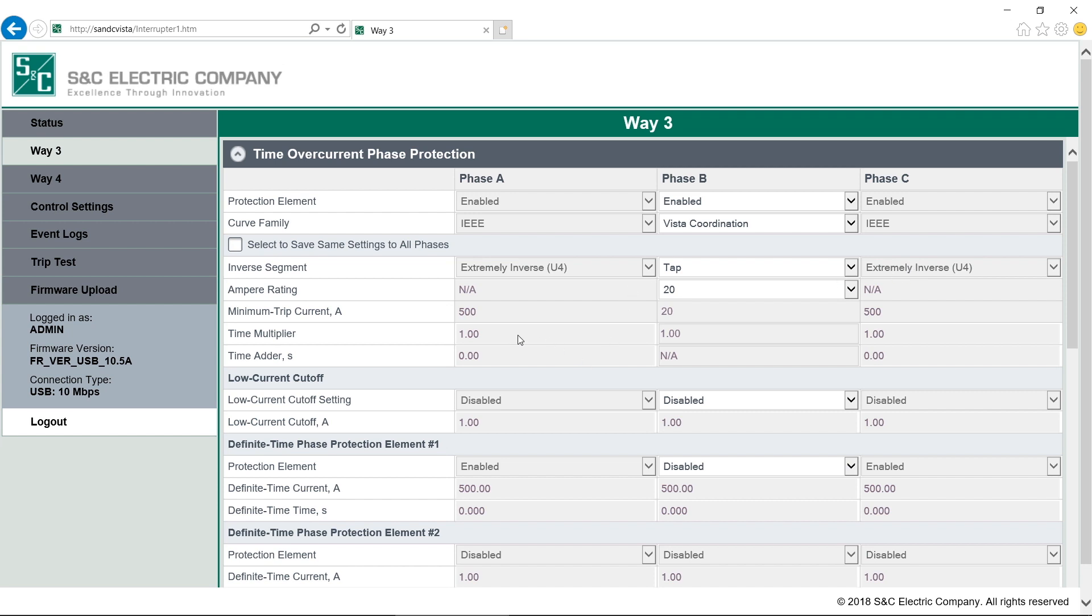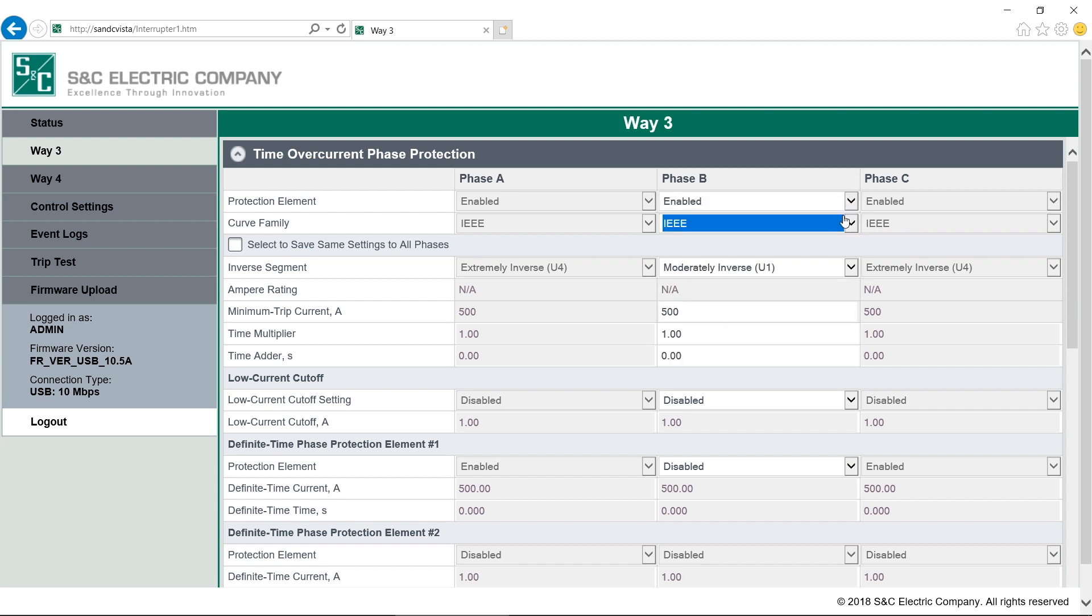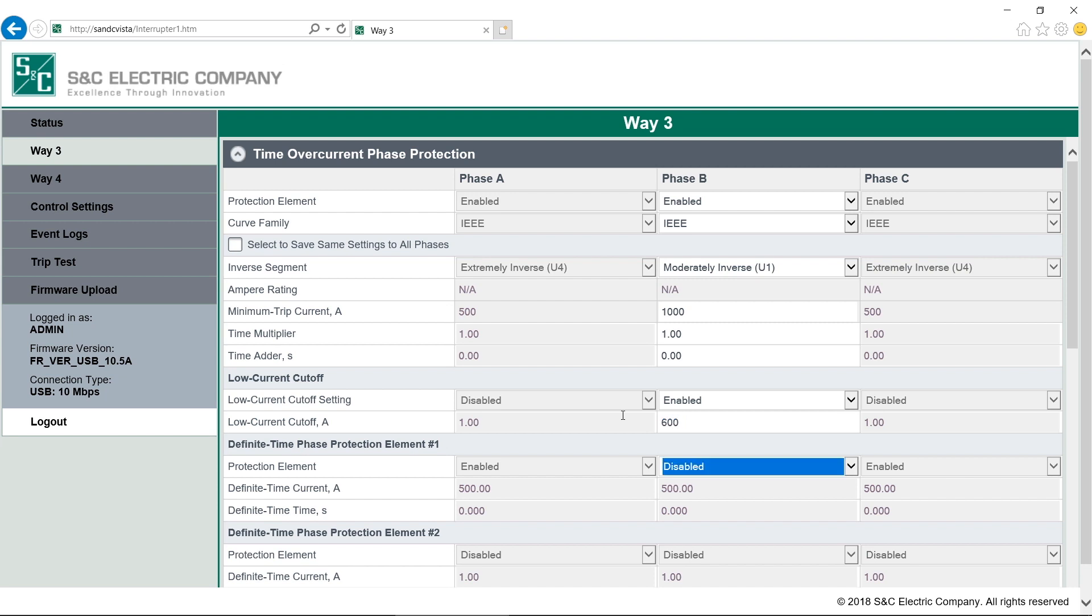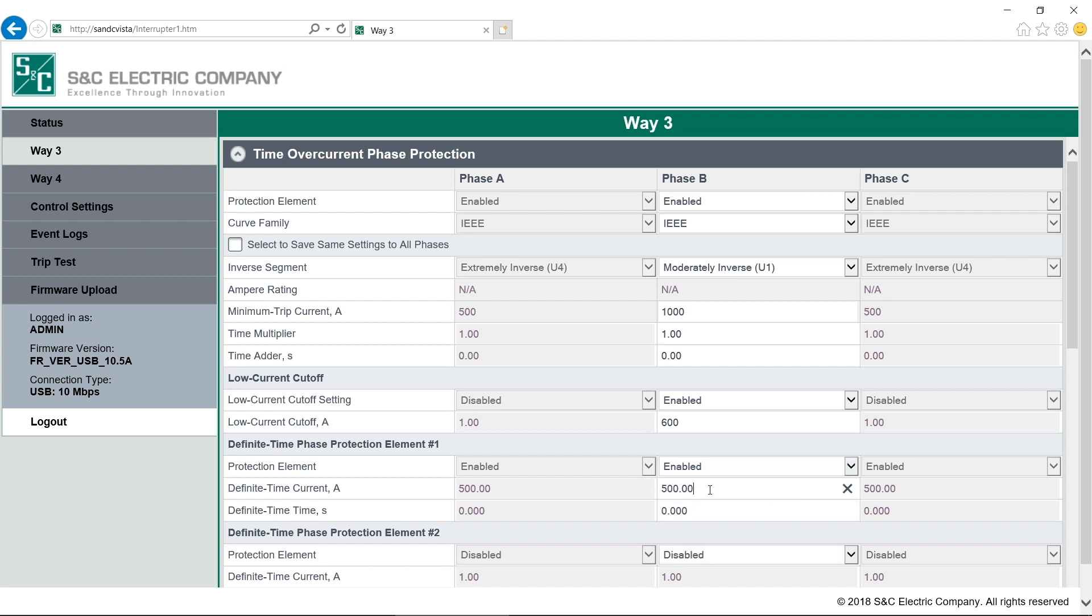If we select a different family, it will make the appropriate attributes editable. If we use the IEEE or IEC curves, the minimum trip current, time multiplier and time adder are available to edit. Available ranges and set points are shown in the written instructions. If we want to add a low current cutoff, we first have to enable the setting and then we can enter a value. This setting is available with all curve families. Definite Time Phase Protection Element 1 and 2 also require us to enable the setting and then enter the associated current and time values. They are available with the VISTA Coordination, IEEE and IEC curve families.